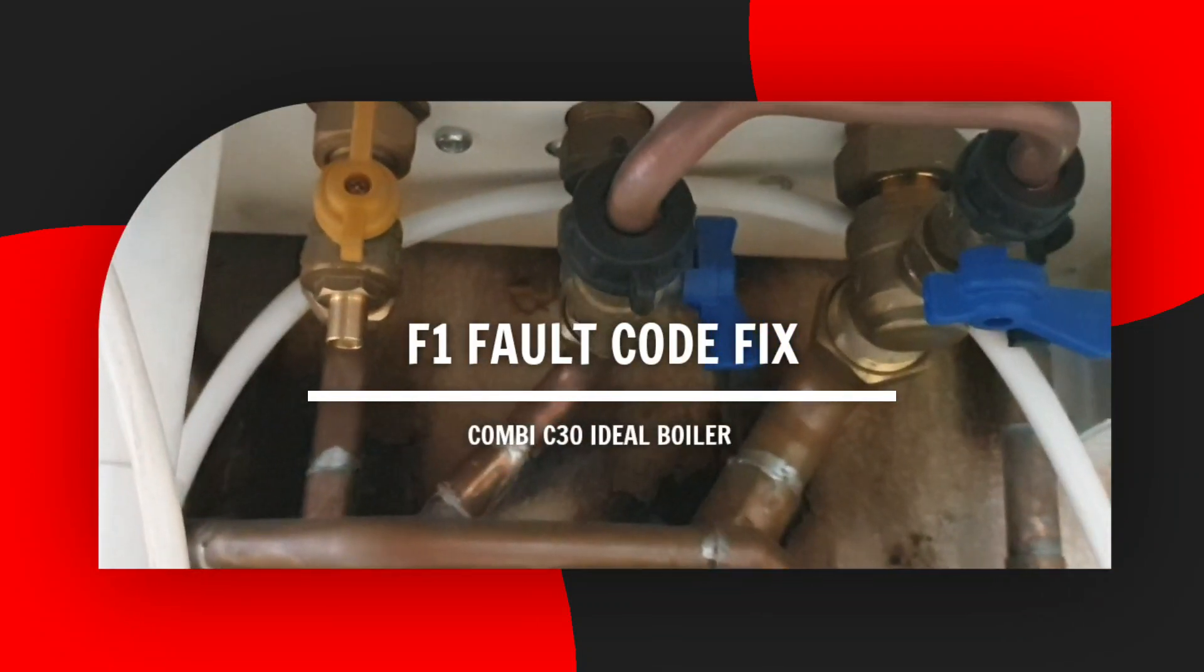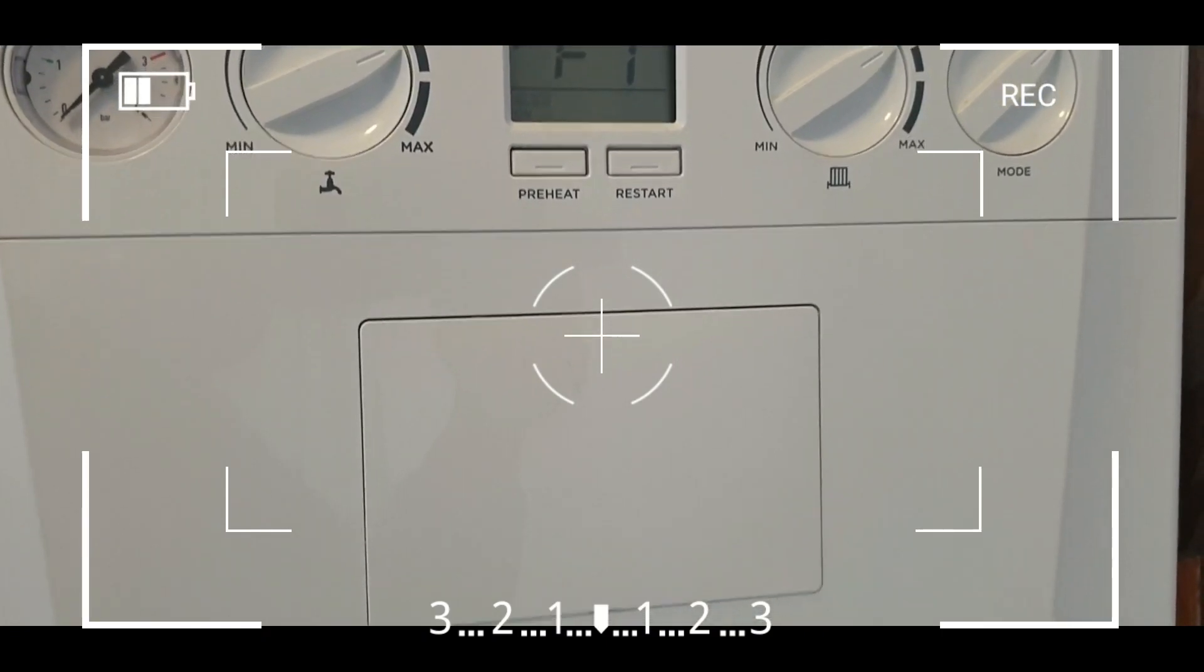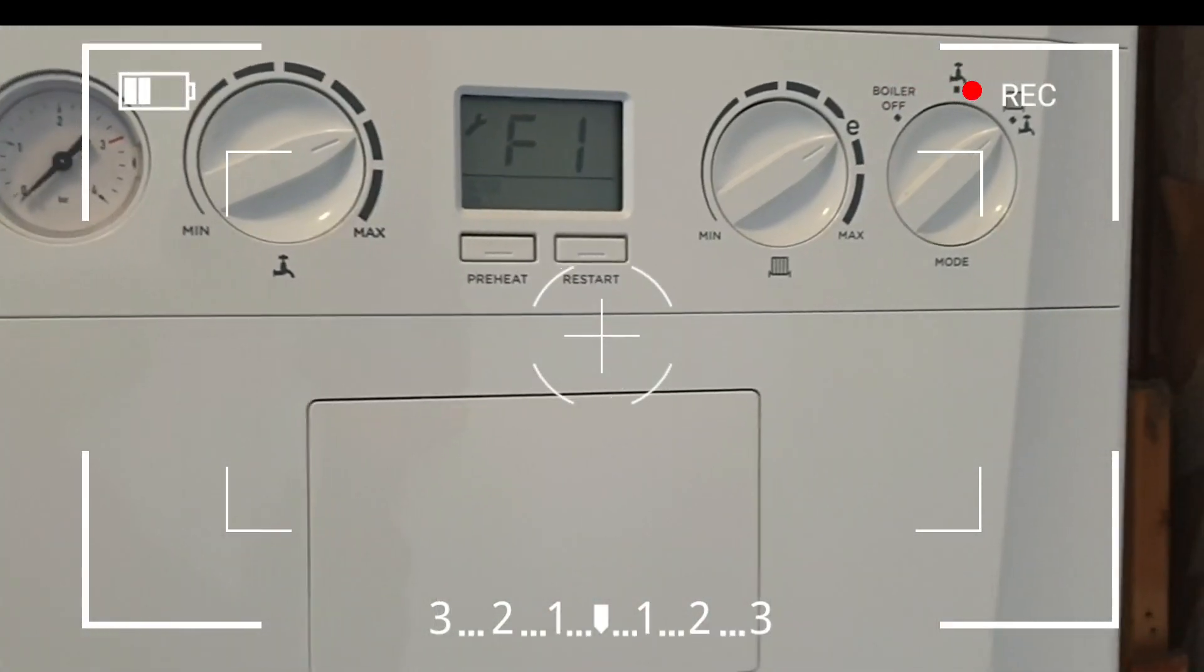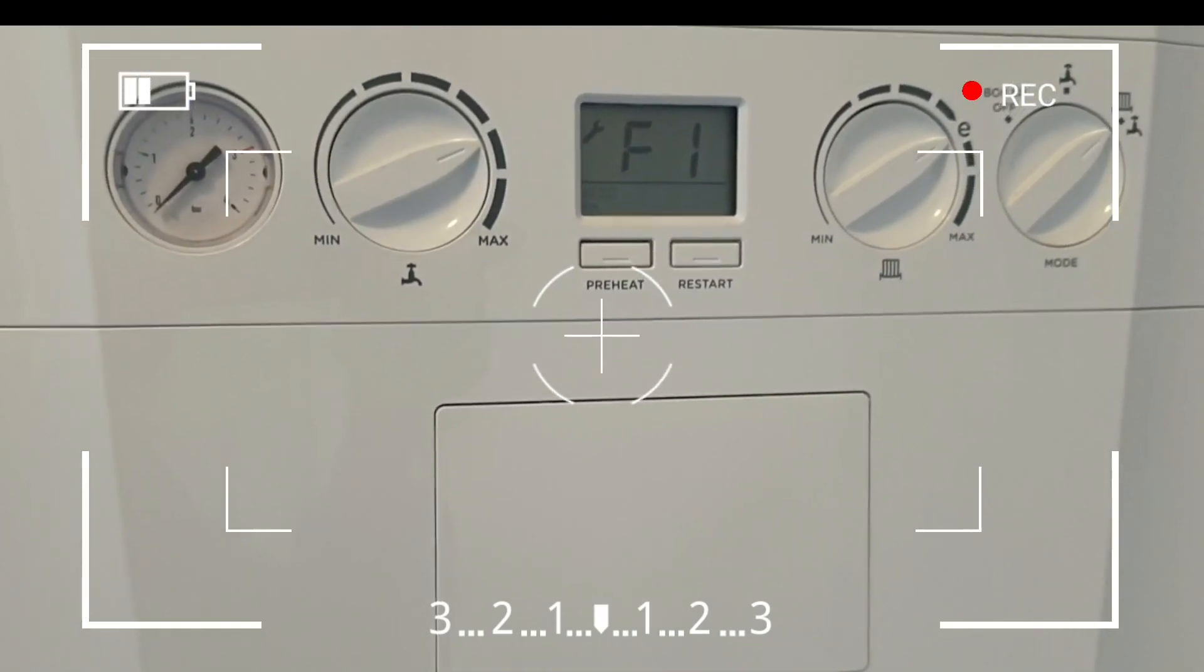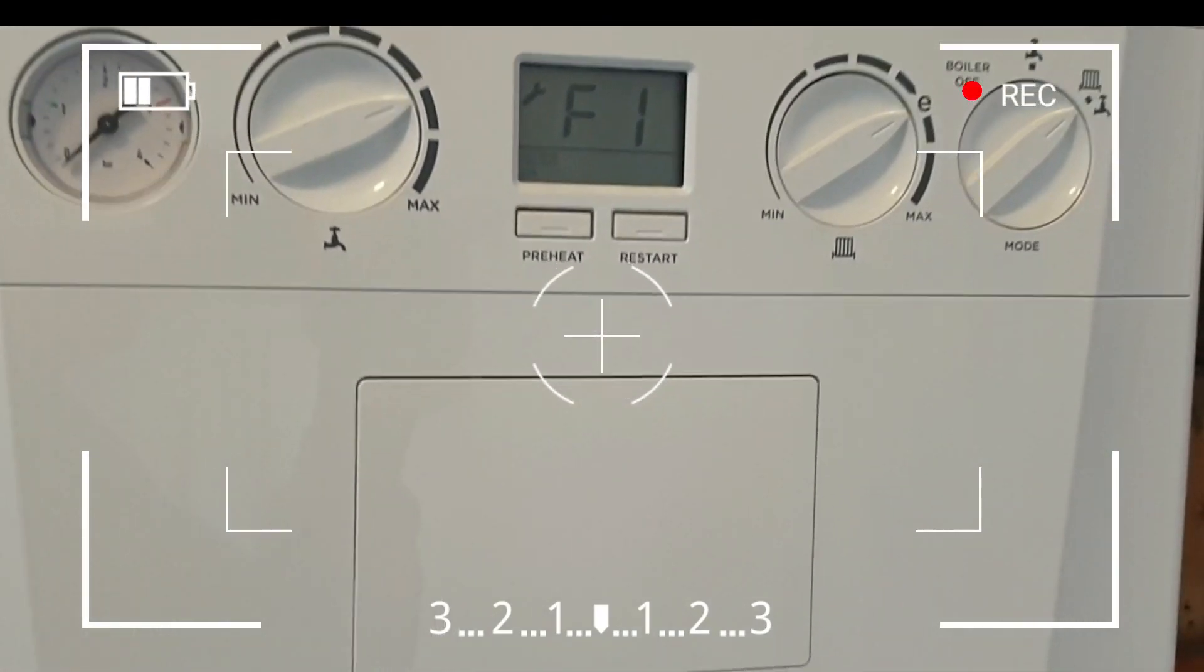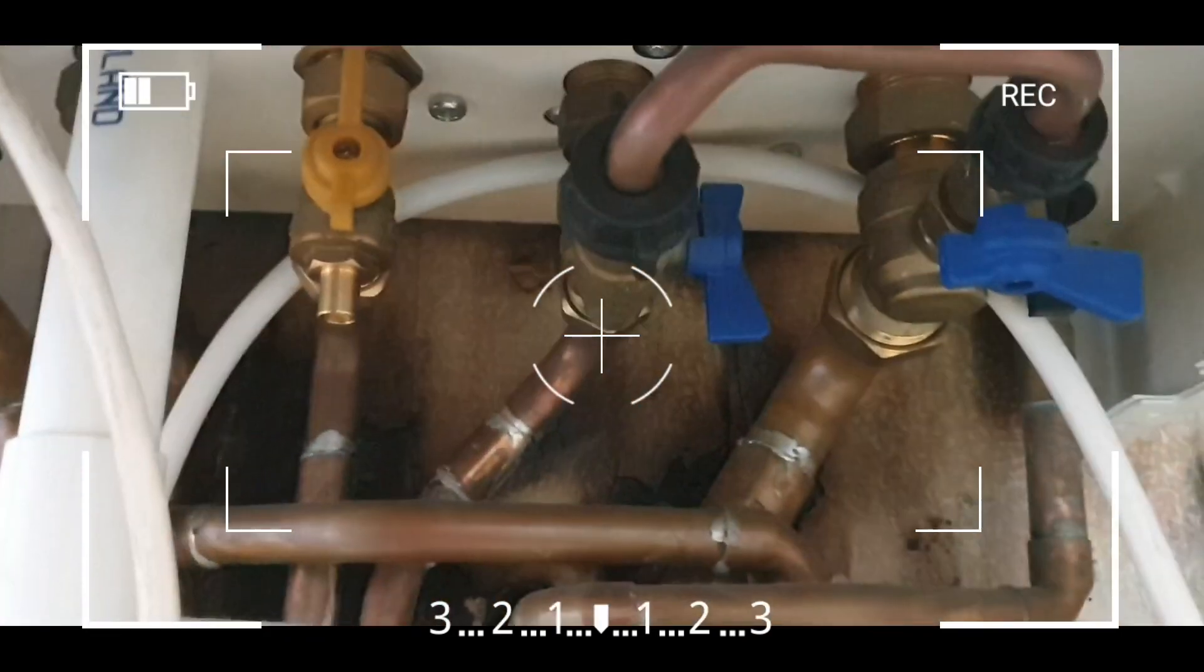What we want to do is flip the two blue valves to positions that would make the needle move to the one bar pressure position to get rid of the F1 fault code. Make sure your boiler is turned off before you perform this fix.